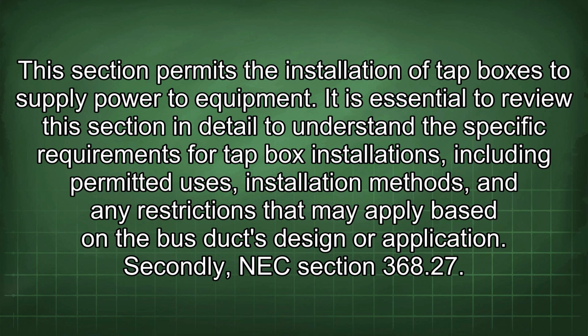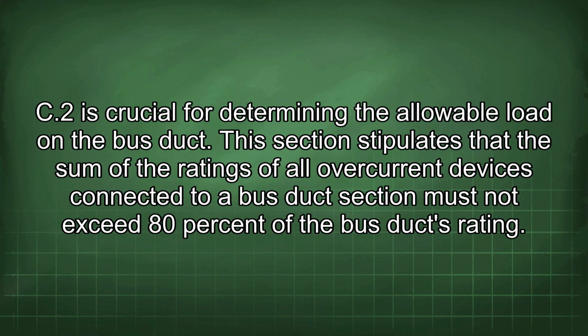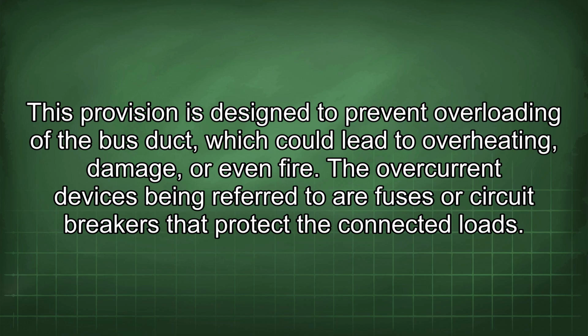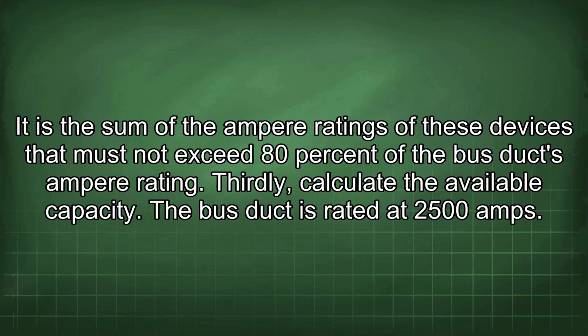Secondly, NEC Section 368.27 C2 is crucial for determining the allowable load on the bus duct. This section stipulates that the sum of the ratings of all overcurrent devices connected to a bus duct section must not exceed 80% of the bus duct's rating. This provision is designed to prevent overloading of the bus duct, which could lead to overheating, damage, or even fire. The overcurrent devices being referred to are fuses or circuit breakers that protect the connected loads. It is the sum of the ampere ratings of these devices that must not exceed 80% of the bus duct's ampere rating.